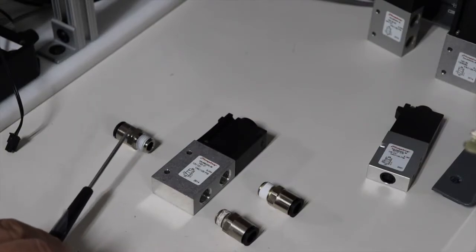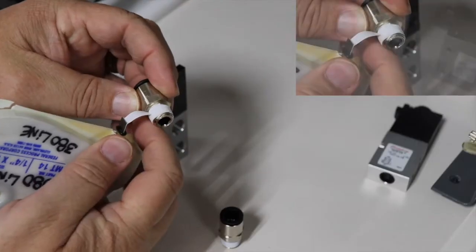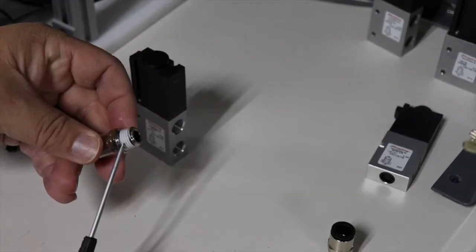Be sure to use thread sealant. The most common sealant options are fittings with sealant pre-applied, Teflon tape, or thread paste. When using thread sealant, be sure to start at the second or third thread to make sure no tape will contaminate your flow path.